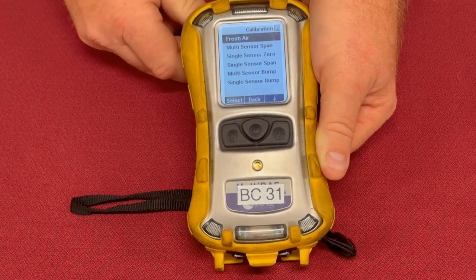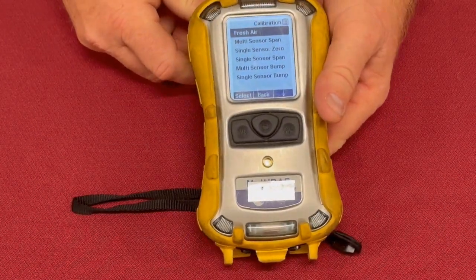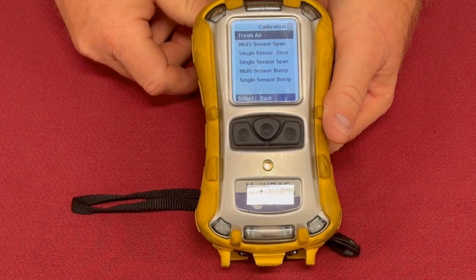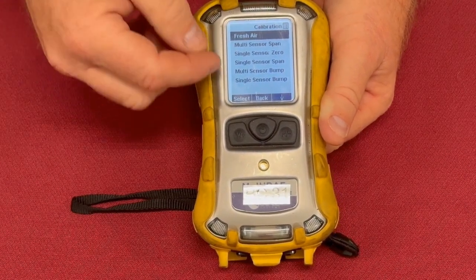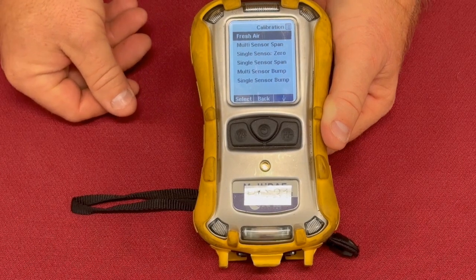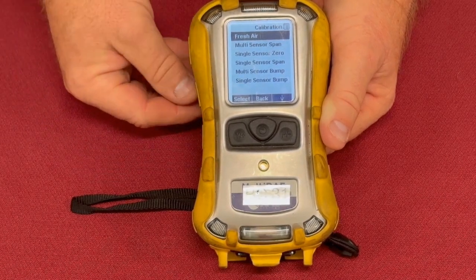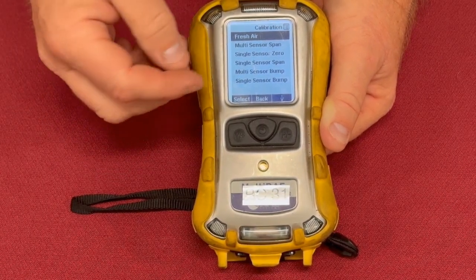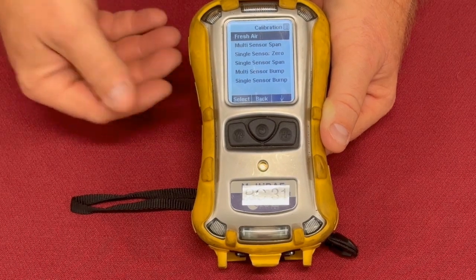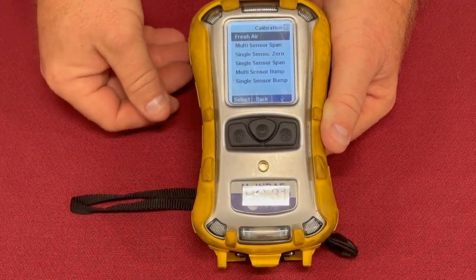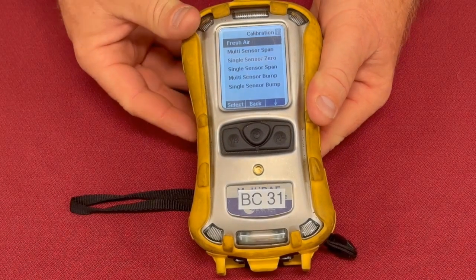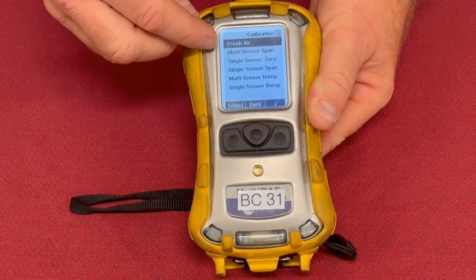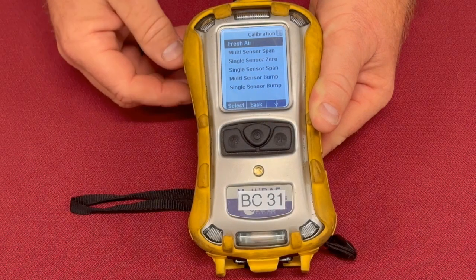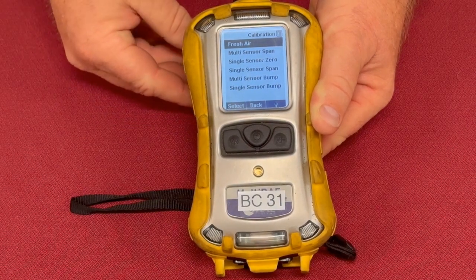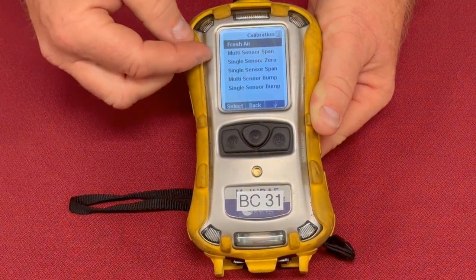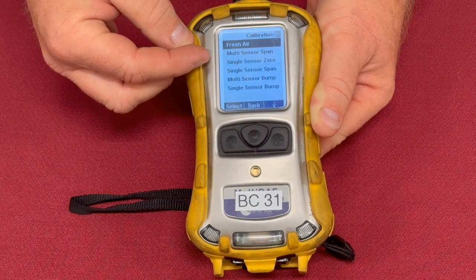Why would you choose the different items? Well, say you had a dirty setup and you wanted to start all over, you could choose one of the single sensors. Or if you think you have a bad sensor and it's already failed an initial test, you can just do the single sensor check to see if that's working properly. But normally what we're going to use is either the multi-sensor span or the multi-sensor bump. Today, since we're doing a calibration, we're going to use the multi-sensor span.